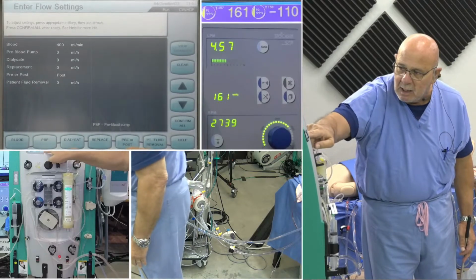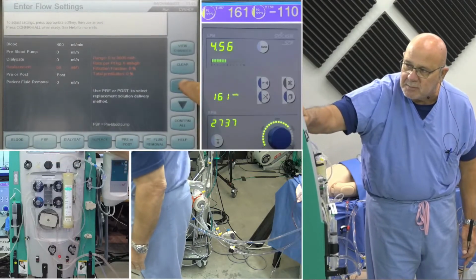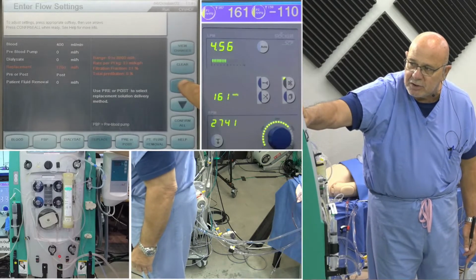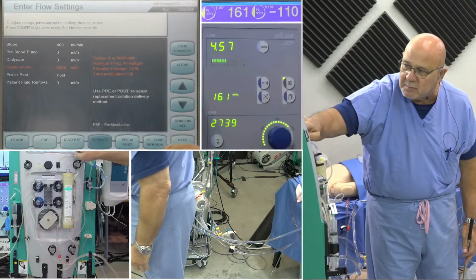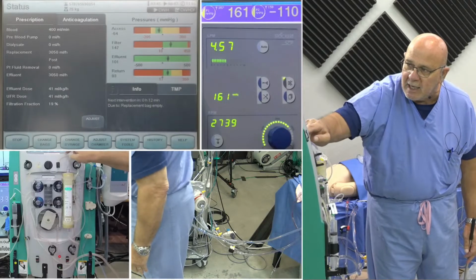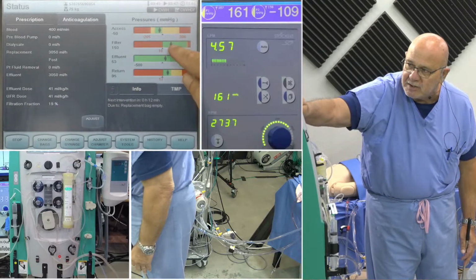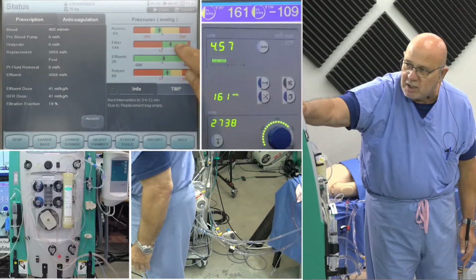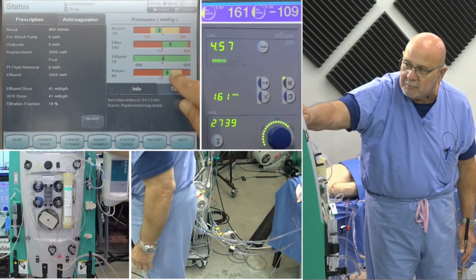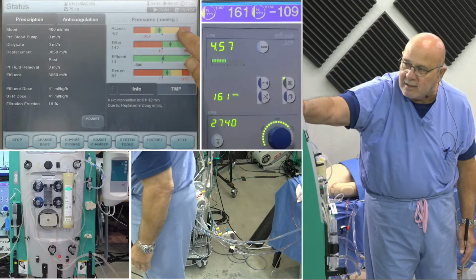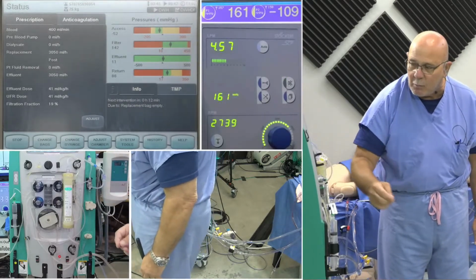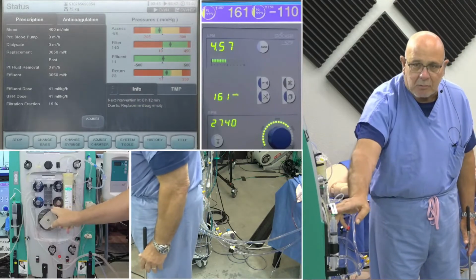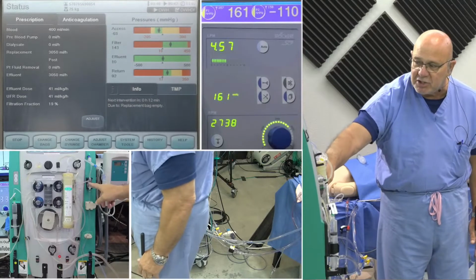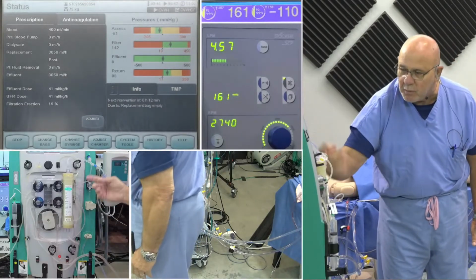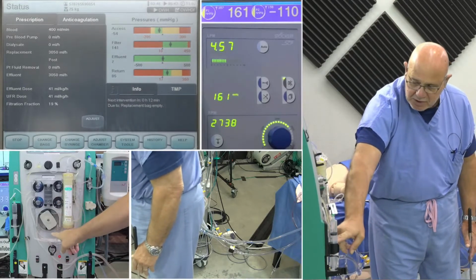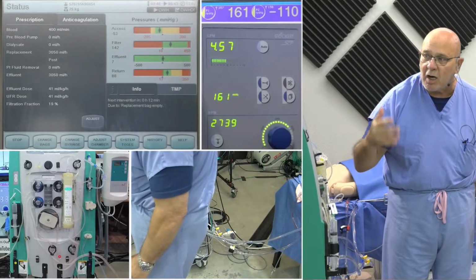So I'll go to adjust, I'll go to replace, I'll turn the replacement on to, let's say 3 liters, which would be a great number for replacement, maybe even more depending on the weight of your patient. And we'll watch what happens to our pressures, and you'll see that it caused our effluent pressure to go down a little bit, our return pressure to come down a little bit, and our access to change a little bit. And that's because now we are adding volume with yet another roller pump into this de-aeration chamber, which is being reflected this way, and all the way back through the circuit before you reach this roller pump. So it's going to have an effect on everything.